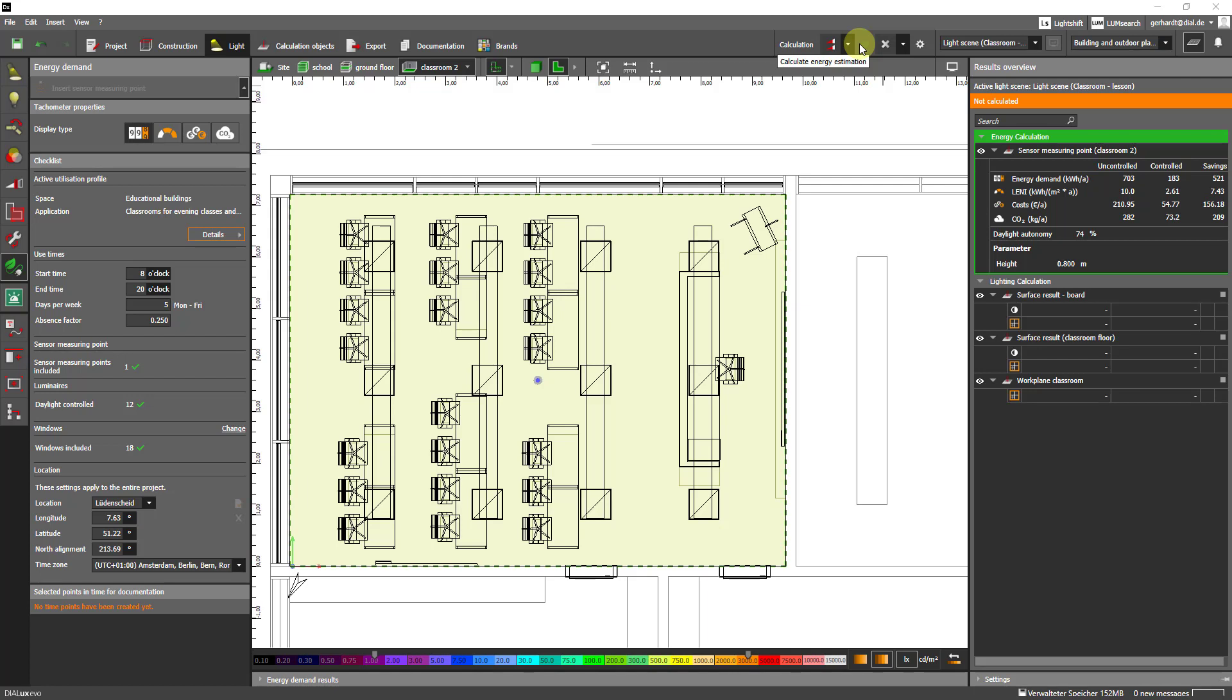So we have an uncontrolled energy demand of 703 kilowatt hours per year and a controlled energy demand of 183 kilowatt hours per year. This results in a saving of 521 kilowatt hours. In addition we see the values per square meter, the costs in euros and the savings of CO2 in kilograms.